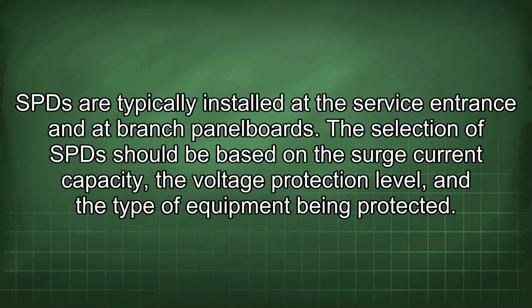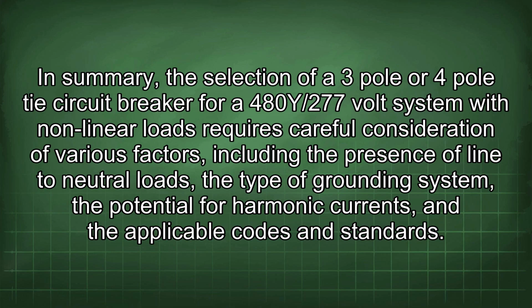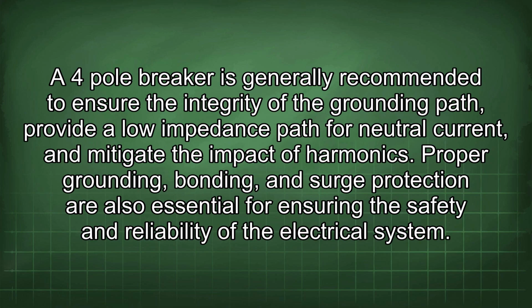In summary, the selection of a 3-pole or 4-pole tie circuit breaker for a 480Y/277V system with nonlinear load requires careful consideration of various factors, including the presence of line-to-neutral loads, the type of grounding system, the potential for harmonic currents, and the applicable codes and standards. A 4-pole breaker is generally recommended to ensure the integrity of the grounding path, provide a low impedance path for neutral current, and mitigate the impact of harmonics.